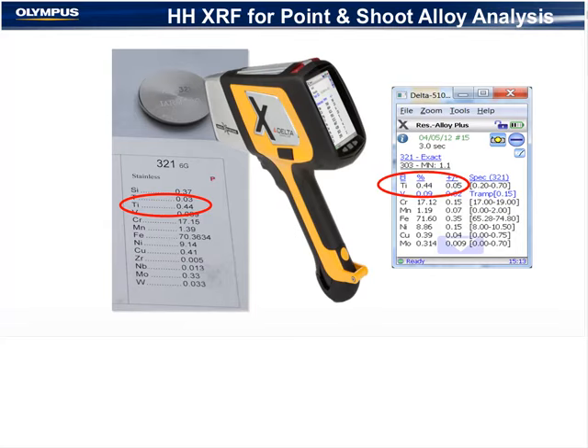The slide shows the analytical performance based on a 3-second analysis. The titanium, which separates stainless 321 from grades 304 or 303, is accurately measured. While this test happened to hit the exact amount of titanium, the precision of the measurement is plus or minus 0.05%. Looking at the chrome level in the same test, we can see that the reading is very accurate as well. The picture on the left is the cert chemistry, and you can see that the actual amount of chrome is 17.15, and then the analysis is showing chrome at 17.12. So you can see we're hitting the numbers pretty much spot on.